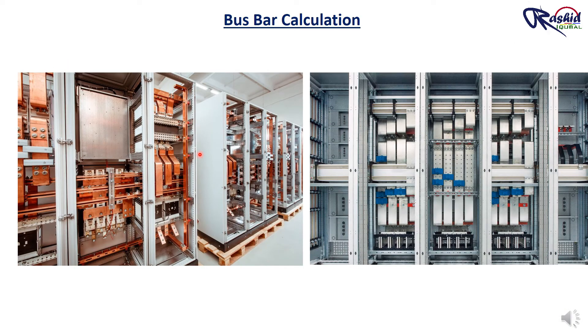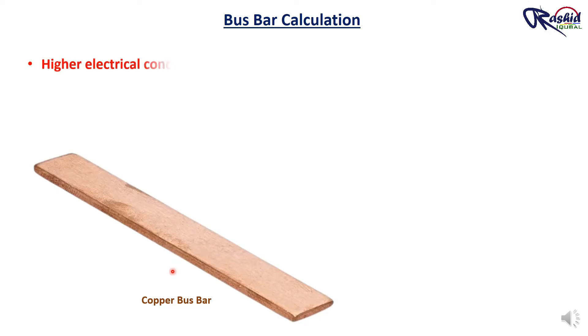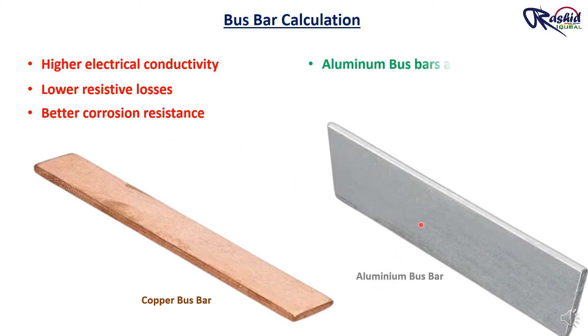Either copper busbar or aluminium busbars. Copper busbars have higher electrical conductivity, lower resistive loss and better corrosion resistance compared to aluminium busbars. However, aluminium busbars are lighter and more cost effective.